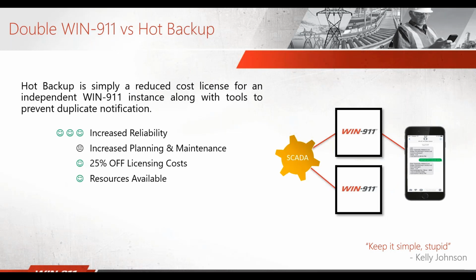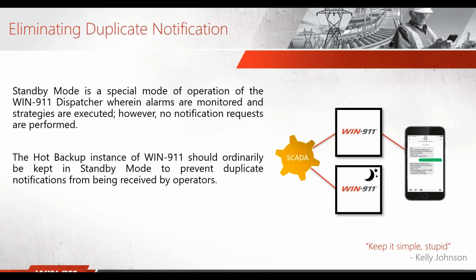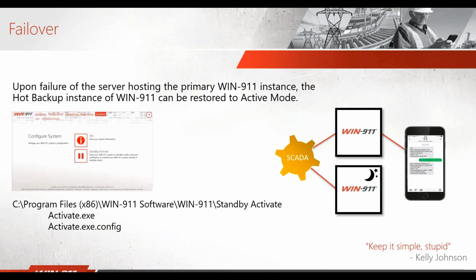So Hot Backup is just a reduced cost license for an independent Win911 instance, along with some tools to make it easy to switch between active and standby modes to prevent duplicate notifications. So how would you do that? Standby mode is a special mode of operation for the Win911 dispatcher. The dispatcher is the piece that controls escalation or notification to operators or contacts. If you put yourself in standby mode, you can still receive alarms from your SCADA system, but you're not sending any notifications out. The Hot Backup instance should ordinarily be kept in standby mode to prevent those duplicate notifications. So you have one primary in active mode and your secondary in standby mode, and only one of them is sending out notifications at a time.